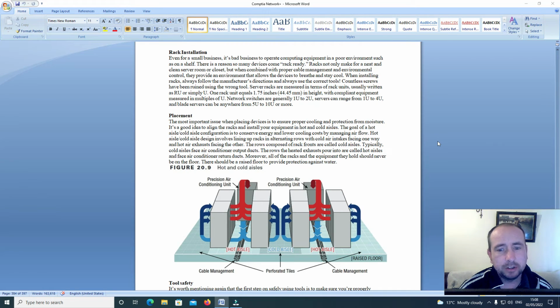Server racks are measured in terms of rack units, usually written as RU or simply U. One rack unit equals 1.75 inches, 44.45 millimeters in height, with compliant equipment measured in multiples of U. Network switches are generally 1U or 2U, servers can range from 1U to 4U, and blade servers can be anywhere from 5U to 10U or more. The most important issue when placing devices is to ensure proper cooling and proper protection from moisture.